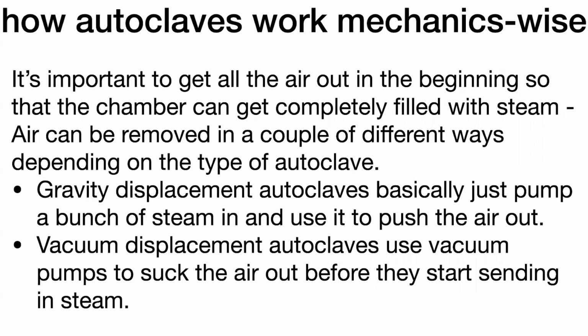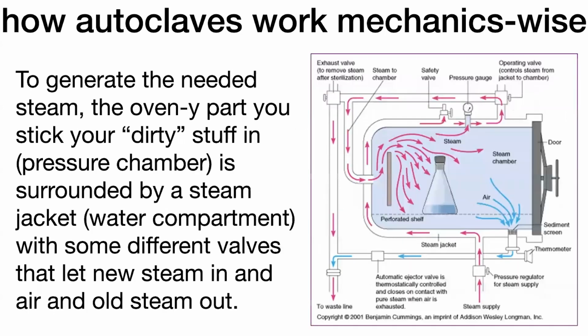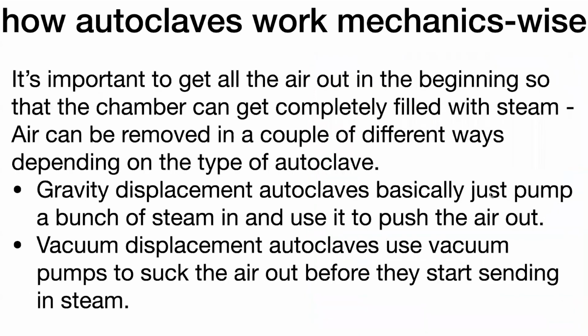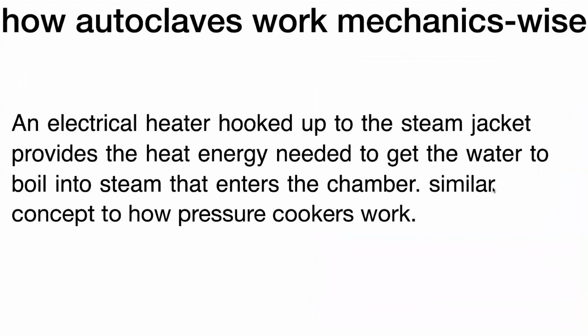One is gravity displacement. So this is a common one where basically you're just pumping in the steam. So in the beginning, you start by pumping in the steam and you have this outlet open. And what's going to happen is that the air is going to get pushed out. This steam is going to be lighter, so it's going to be on top of the air, and it's going to push the air down and into that outlet valve and get rid of that air. With a vacuum displacement autoclave, you're going to use vacuum pumps to actually suck the air out before you start sending in the steam.